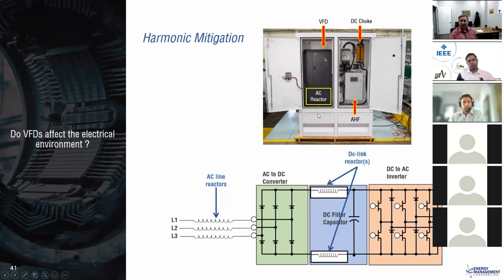We wanted to apply an active harmonic filter, which had usually been the most expensive type of harmonic mitigation, but one that's starting to become very, very popular now. Again, we've got graphs that compare costs. So the topology was: we had this AC inductor here as standard, and we applied this active harmonic filter, which we'll get into in a minute.